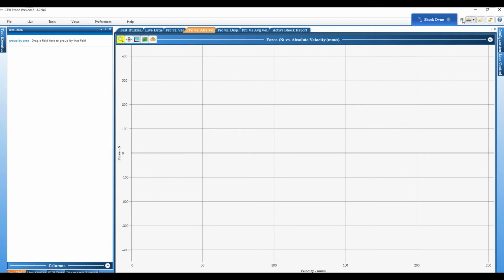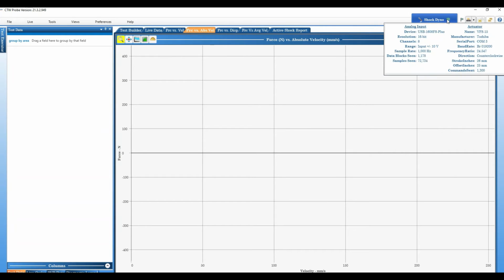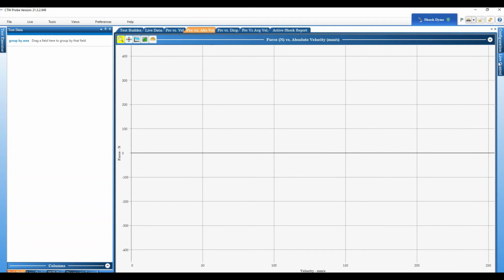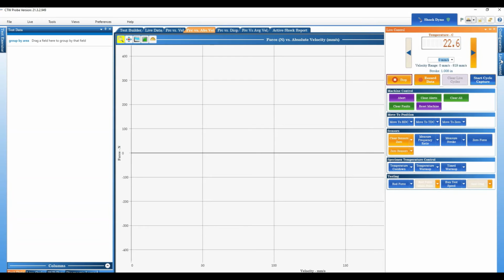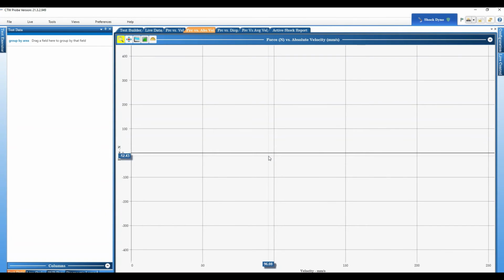The green flag is for the key. Make sure you have your key plugged in, because obviously you can't collect data without the key. You can use the software, you just can't collect new data. And the green shield. Then you want to go to Live Control, and you want to do a measure stroke, because you want the dyno to measure the stroke so that it's ready to run. So I'm going to click yes, it's going to run. You'll hear it in the background.